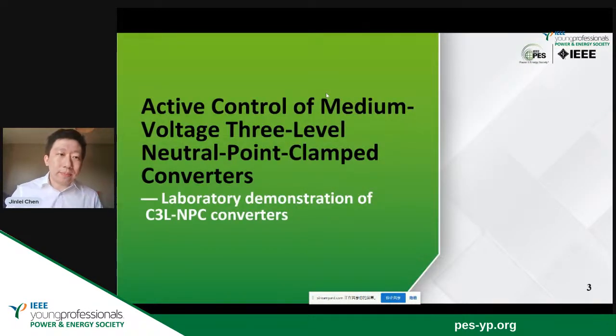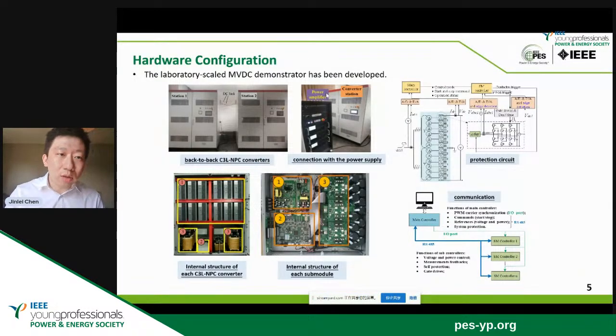So in the first stage, we developed a laboratory-scaled MVDC testbed. This is the hardware configuration of the MVDC testbed. In the first picture, there are back-to-back three-level NPC converter stations. We omitted the DC impedance and just connected them together. In the second picture, we connected the boxes to the power supply. This power supply adopts a power amplifier. This is a controllable power source. It can be controlled by the OPAL-RT to mimic different conditions of the AC grid.